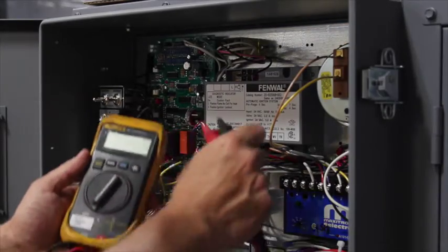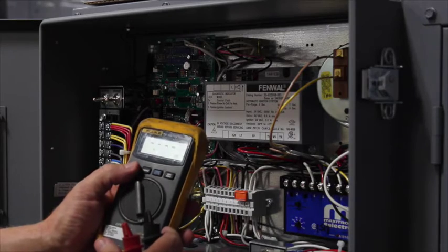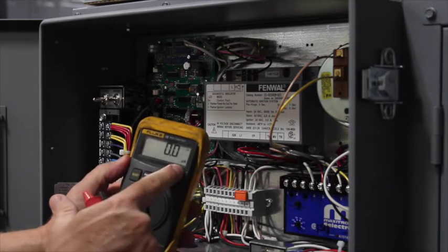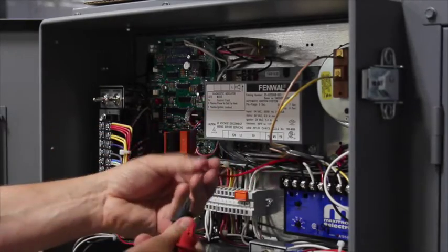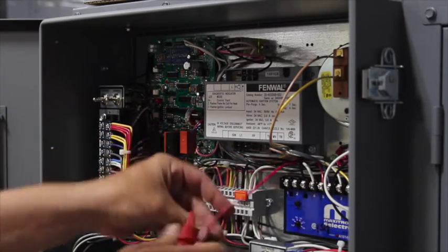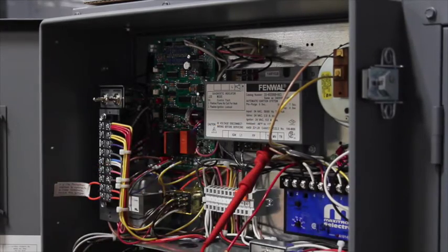When performing startup, you must first connect your DC microamp meter to the flame safeguard relay. Verify the meter is on DC microamps. Remove the red wire from the Fenwal board and connect your black lead with clip to the push-on and your red lead with clip to the spade of the board.